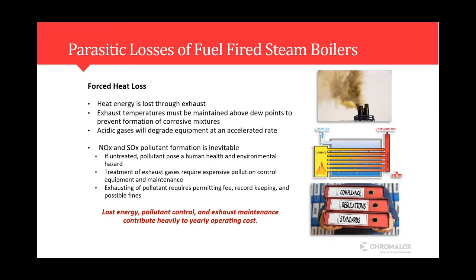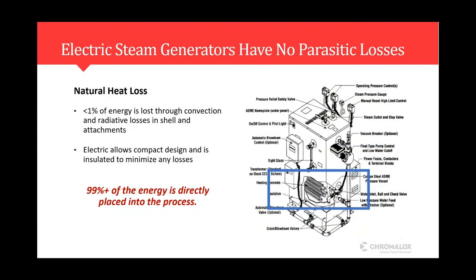So it's parasitic, but it's necessary to keep these systems operating. On the electric side, it's very minimal, the type of parasitic losses we see. Just inherently with how the electric heating systems work, the elements are submersed in the fluid. So that means that the heat generation is being done within, which the heat has nowhere to go but into the process. So really the only parasitic losses you might see are on the exterior shells through heat losses. But traditionally these systems are insulated, and that prevents too much of those heat losses. So really we attribute this to about less than 1% is typically going to be lost from parasitic losses on the electric side. So from that aspect, you have a lot more energy savings, just keeping the energy where it's needed and the heat where it's needed, which of course is your process.